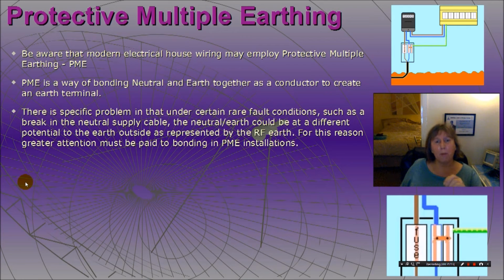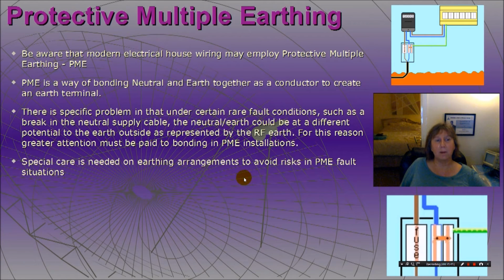There is a specific problem here - some rare fault conditions, such as a break in the neutral supply cable somewhere along the line. The neutral earth could then be at a different potential to the earth outside, as represented by the RF earth inside. For this reason, you've got to pay particular attention to the bonding in PME installations, taking special care on those earthing arrangements to avoid risks in a PME fault situation.